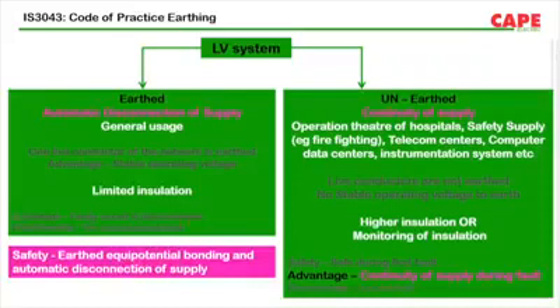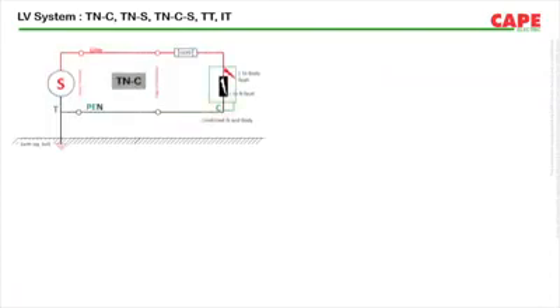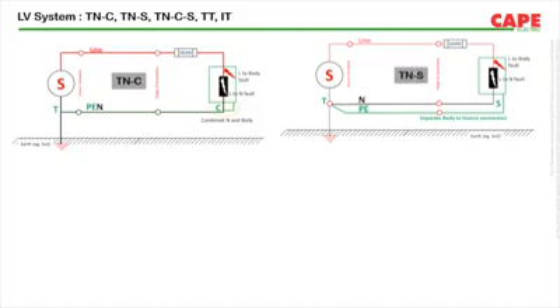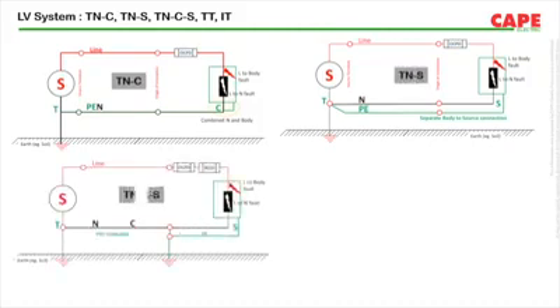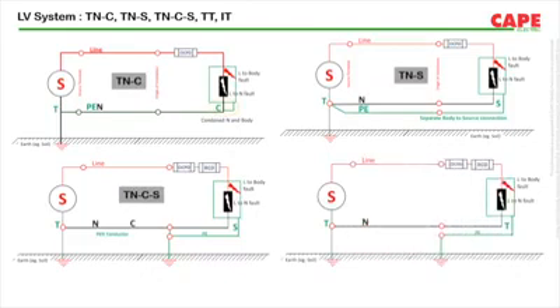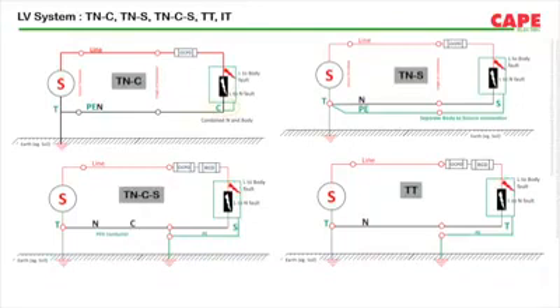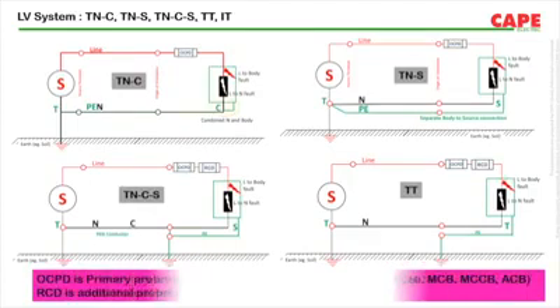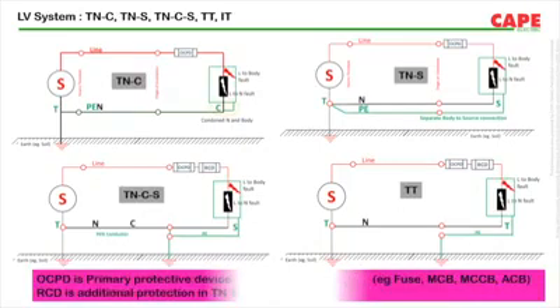Safety is achieved by earthed equipotential bonding and automatic disconnection of supply in an earthed system. For the purpose of achieving a high degree of safety, low voltage systems are categorized as TNC, TNS, TNCS, TT, and IT. Each network behaves in a typical fashion, and the way of handling each network is different. The basic concept followed in our standards is that OCPDs, such as MCB, MCCB and fuse, are the primary protective device, and RCD is for additional protection.